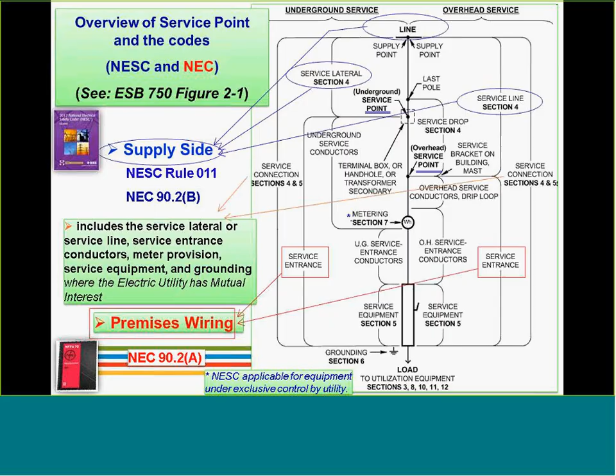If you are connecting a standard distribution service, every standard distribution service requires service protection or service equipment, which is basically a disconnect and your main overcurrent protection. That also pertains to distributed generation, so that's a similarity between the two. Also between the two, we need to make sure the billing meters are secure, so we're properly billing, or in some cases paying for the generation that's out there. And we need to make sure our interface points are clear on where the PCC is and who owns what, so we don't have potential safety and operational problems.